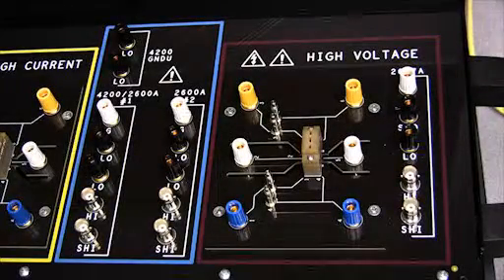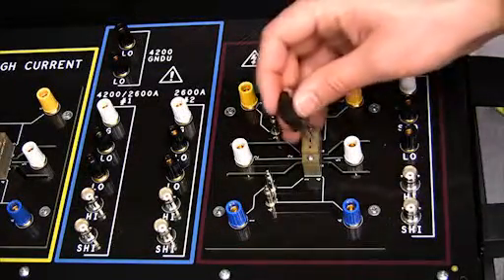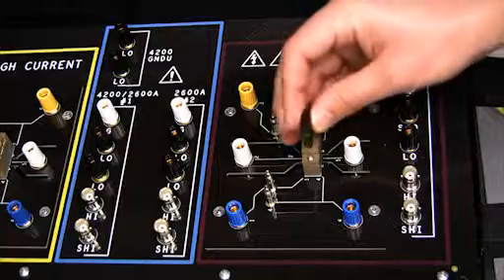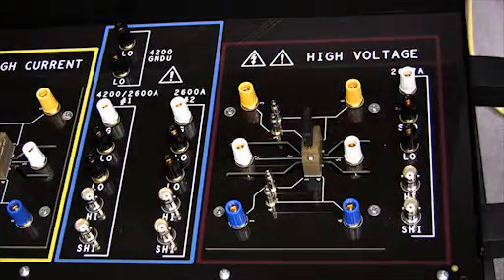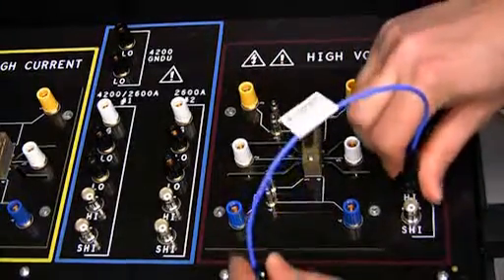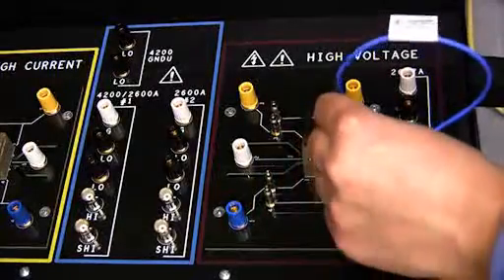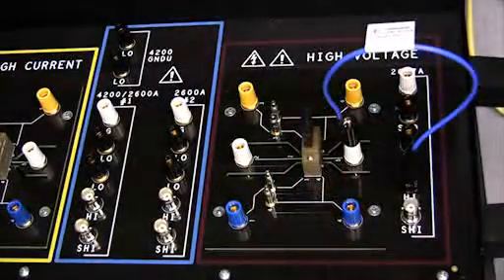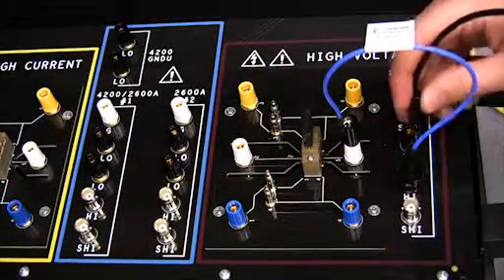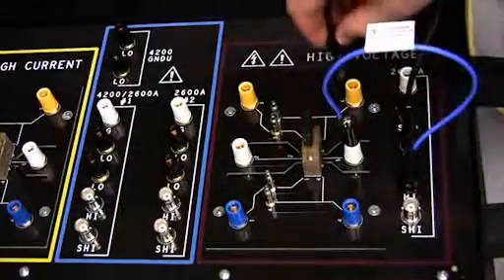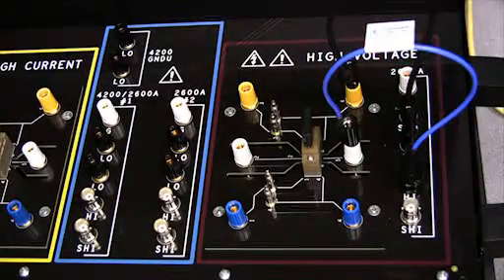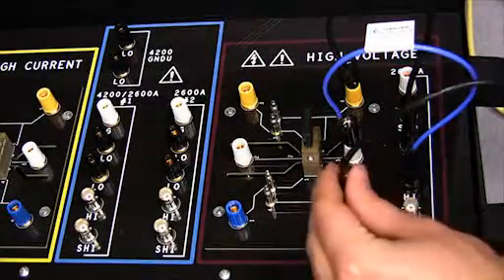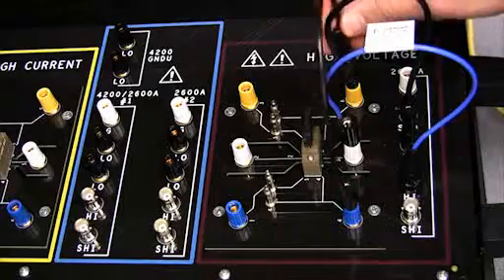Third, place the device in the test socket and route the signals to the device. The high terminal of the source meter instrument is routed to the collector of the device while the low terminal is routed to the emitter. The gate of the device is tied to the emitter ensuring that the gate to emitter voltage remains at zero.